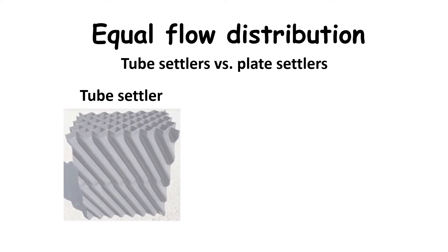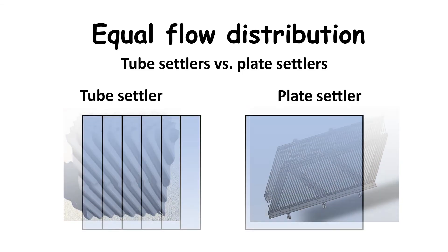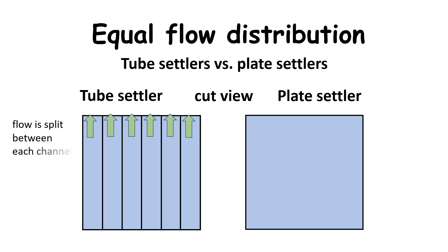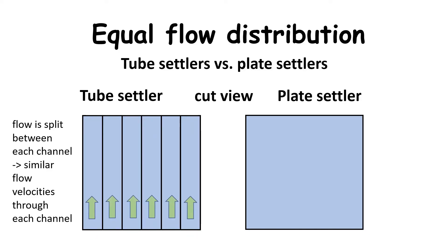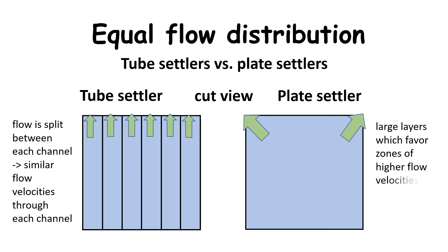Tube settlers have, in general, an advantage over plate settlers regarding equal flow distribution. Because tube settlers consist of several smaller channels, the water flow is split between each channel, resulting in similar flow velocities throughout each channel. However, plate settlers consist of large layers, which favour zones of higher flow velocities, short-circuiting, and zones of little or no upward flow velocity at all — dead zones.